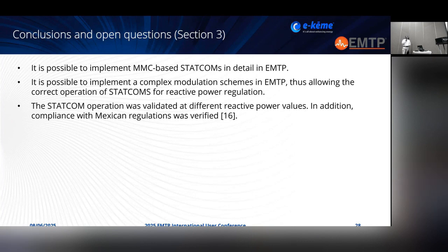For section number 3, we have some conclusions and open questions. It is possible to implement MMC-based STATCOMs in detail in EMTP. It is possible to implement complex modulation schemes in EMTP and validate them, thus allowing us to operate the STATCOMs for reactive power regulation and any other functions. It's also possible to validate the STATCOM at different reactive power values or set points, and this was in compliance with the Mexican regulations.